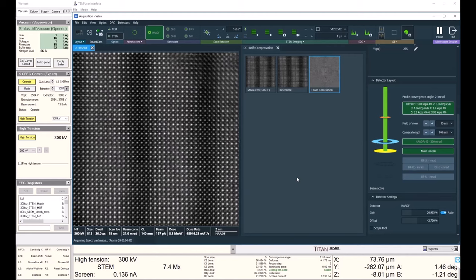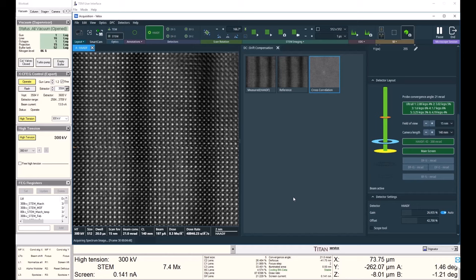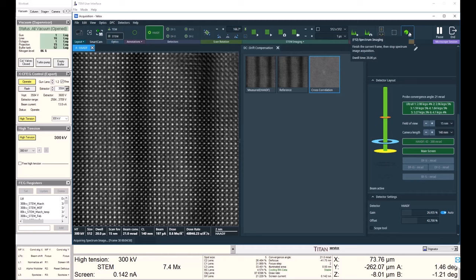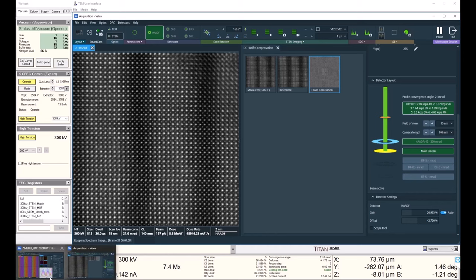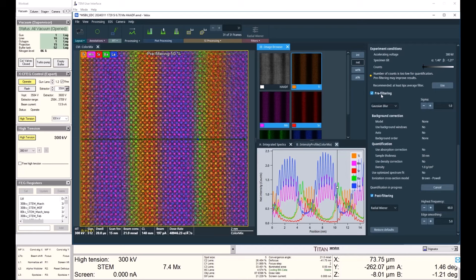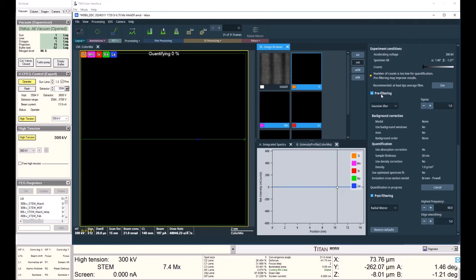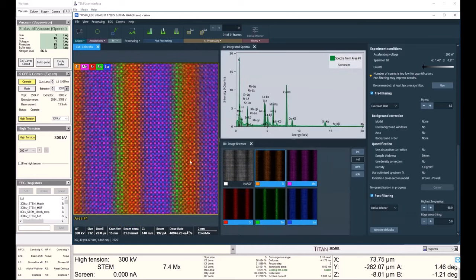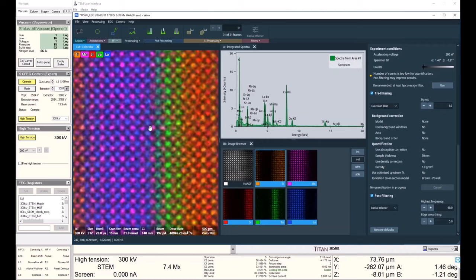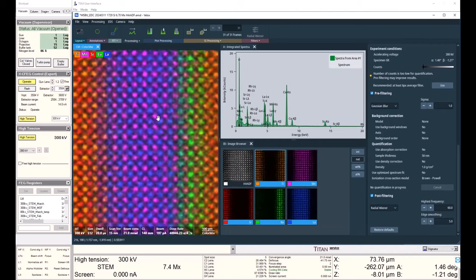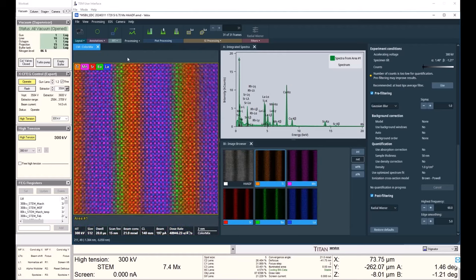And we've been acquiring for just about five minutes, we'll take one more frame after this one. And once the acquisition is complete in VELOX and the file is saved, we can do the finishing touches on our map. One of them is to apply a pre-filter, which is one of the simple options we have to improve quantification. Another would be to use a spectrum profile instead of the intensity profile we use today. This is important to get good quantification, and you can see the video about using a spectrum profile on our YouTube channel. The pre-filter has been applied, and this will really make all of our atoms come through super beautifully in this really nice lamella sample here with all these distinct layers that our Ultra X has captured so nicely.